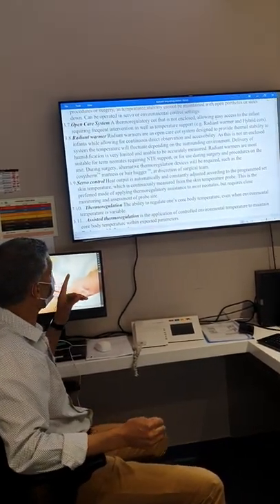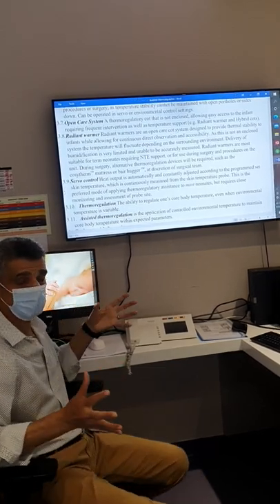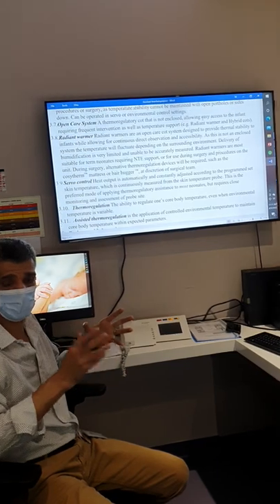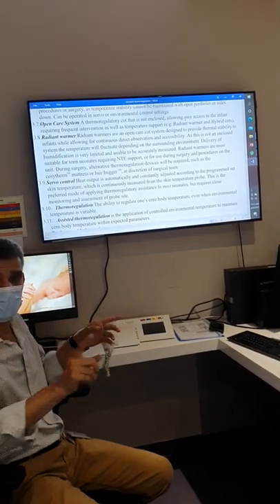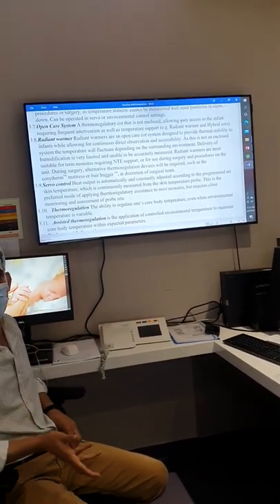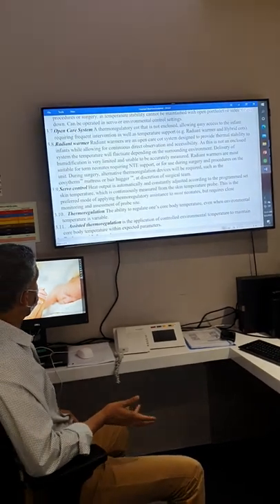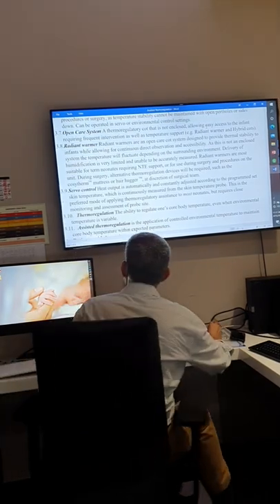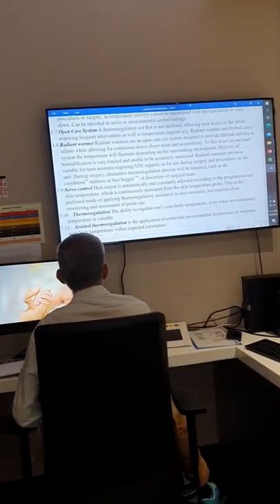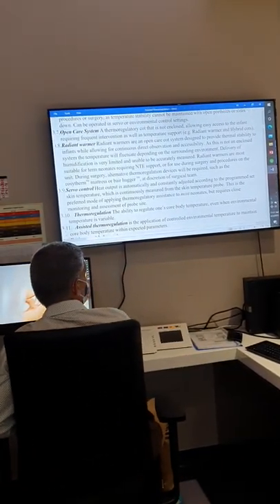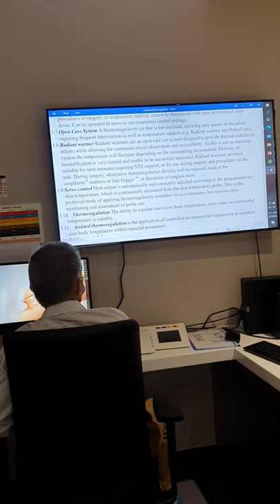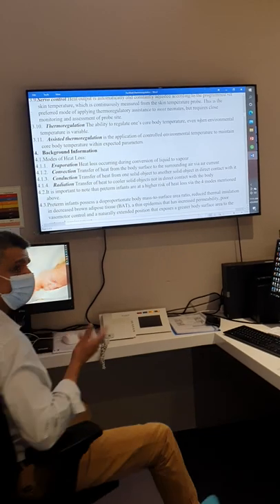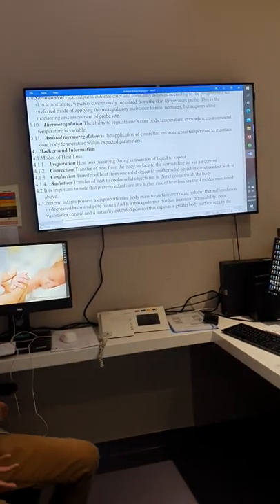Thermoregulation or servo control means the heat output inside the environment, such as the incubator, is controlled automatically by temperature recording from the baby. We have self-control thermoregulation and assisted thermoregulation — the help we provide to maintain the patient's temperature.